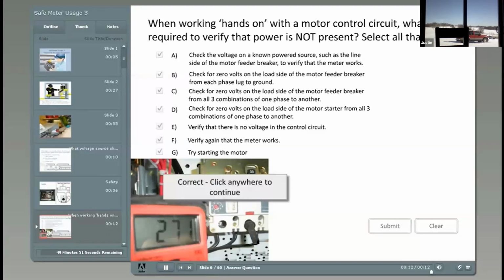The correct answers are A, check the voltage on a known powered source, such as the line side of the motor feeder breaker, to verify that the meter works. B, check for 0 volts on the load side of the motor feeder breaker from each phase lug to ground. C, check for 0 volts on the load side of the motor feeder breaker from all 3 combinations of one phase to another. D, check for 0 volts on the load side of the motor starter from all 3 combinations of one phase to another.